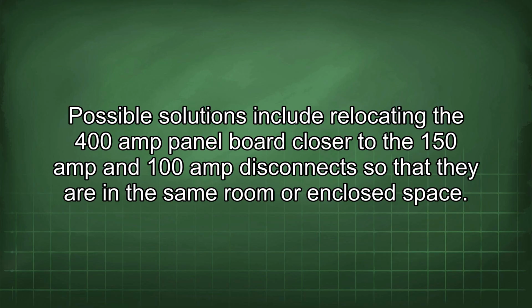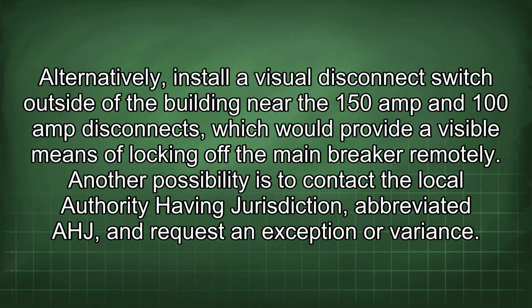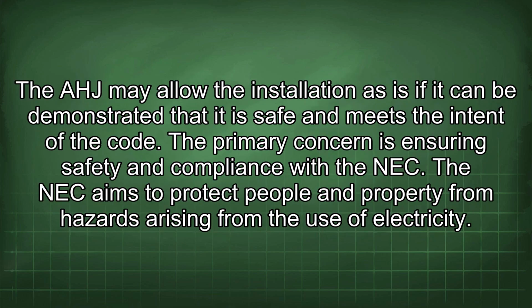Possible solutions include relocating the 400 amp panel board closer to the 150 amp and 100 amp disconnects so that they are in the same room or enclosed space. Alternatively, install a visual disconnect switch outside of the building near the 150 amp and 100 amp disconnects, which would provide a visible means of locking off the main breaker remotely. Another possibility is to contact the local authority having jurisdiction, abbreviated AHJ, and request an exception or variance. The AHJ may allow the installation if it can be demonstrated that it is safe and meets the intent of the code. The primary concern is ensuring safety and compliance with the NEC.